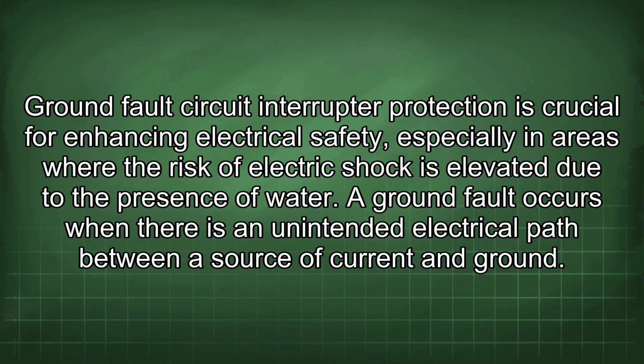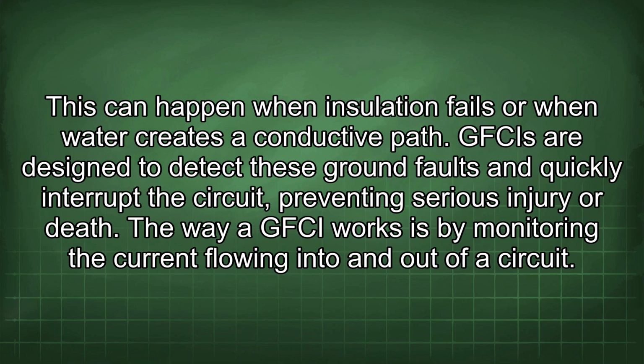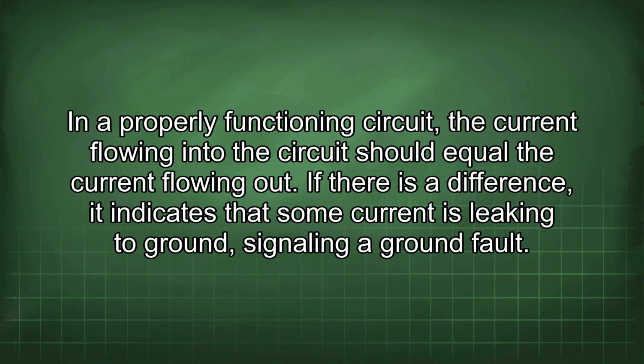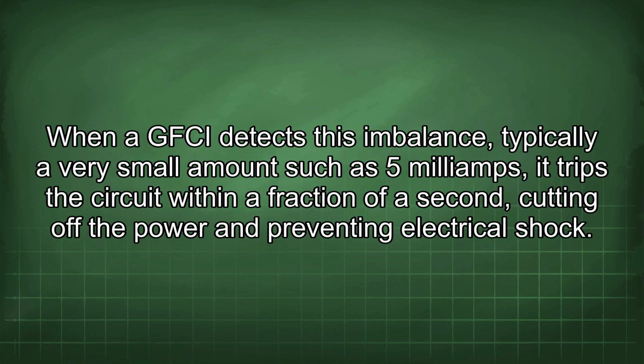A ground fault occurs when there is an unintended electrical path between a source of current and ground. This can happen when insulation fails or when water creates a conductive path. GFCIs are designed to detect these ground faults and quickly interrupt the circuit, preventing serious injury or death. The way a GFCI works is by monitoring the current flowing into and out of a circuit. In a properly functioning circuit, the current flowing into the circuit should equal the current flowing out. If there is a difference, it indicates that some current is leaking to ground, signaling a ground fault. When a GFCI detects this imbalance, typically a very small amount such as 5 mA, it trips the circuit within a fraction of a second, cutting off the power and preventing electrical shock.